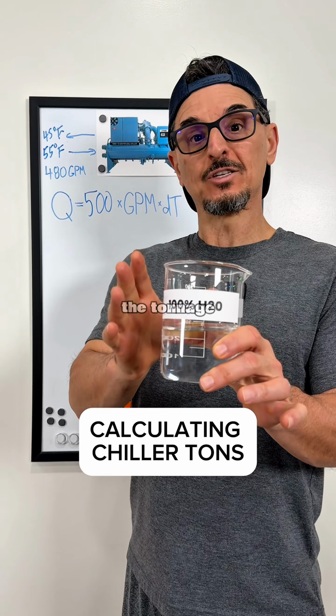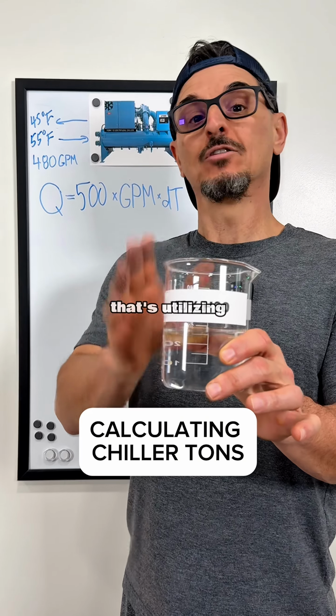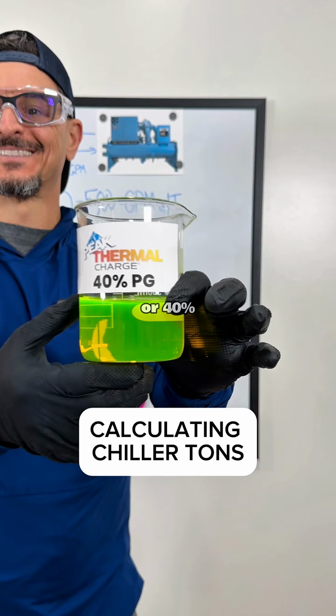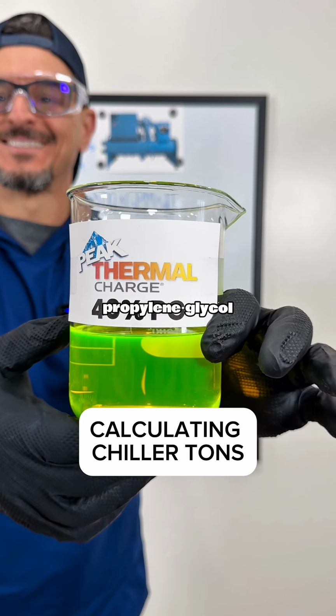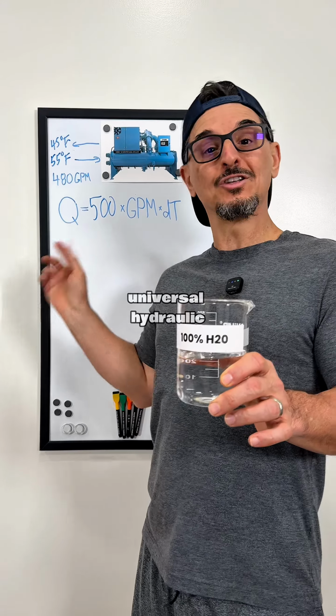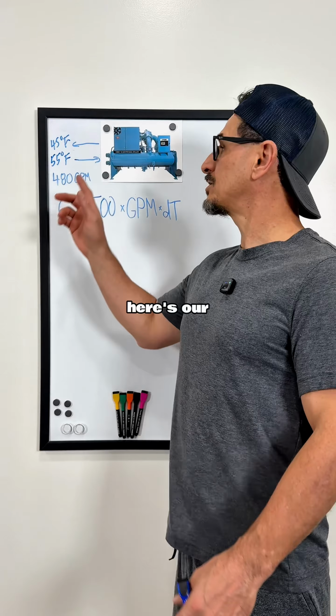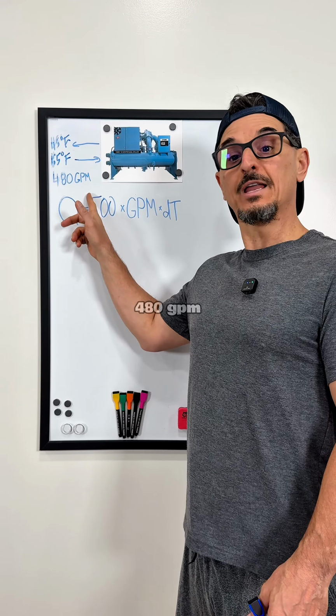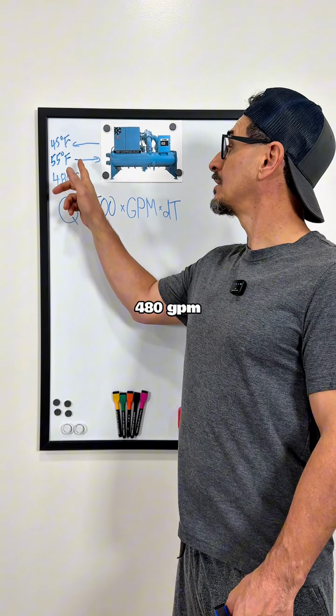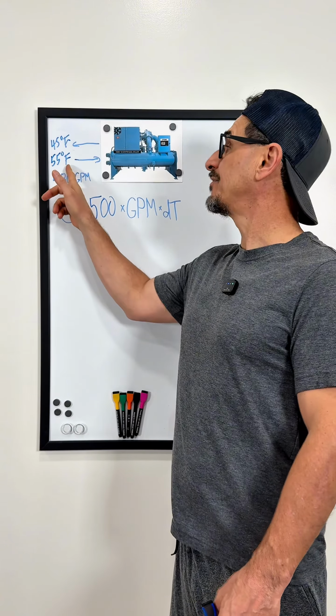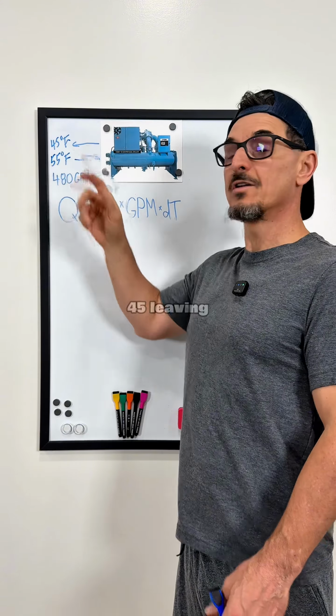Here's how to calculate the tonnage of your chiller that's utilizing either water or 40% propylene glycol solution using the universal hydronic formula. Here's our chiller example. We have 480 GPM going through the evaporator. We have 55 degrees entering and 45 leaving.